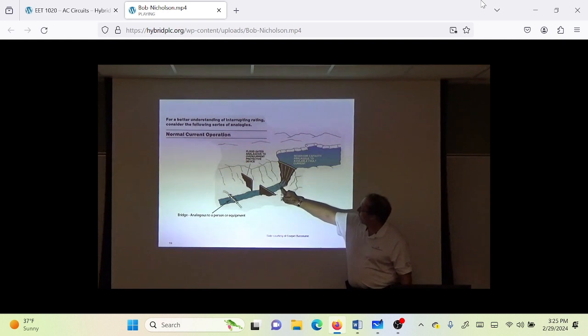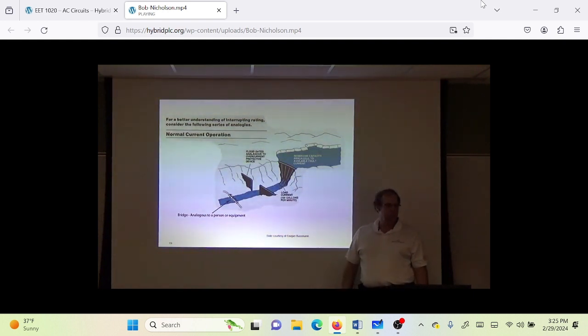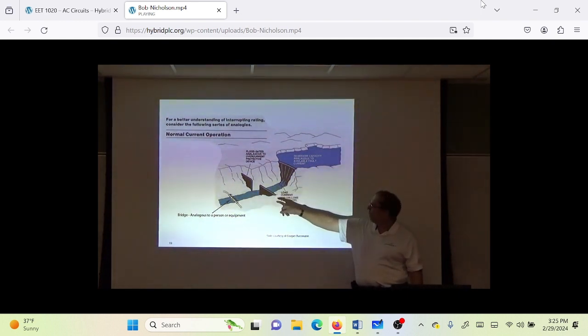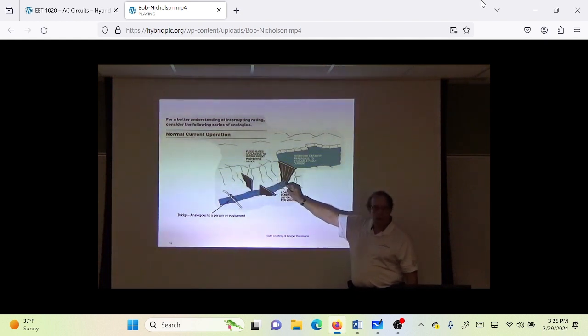It goes down a wire, so you know what impedance is, correct? Impedance is going to start knocking down the fault current. Think of it, resistance, impedance. So the longer this is and the smaller the wire, it's going to start changing the amount of energy that's going to move down the wire. So that water is a wire.